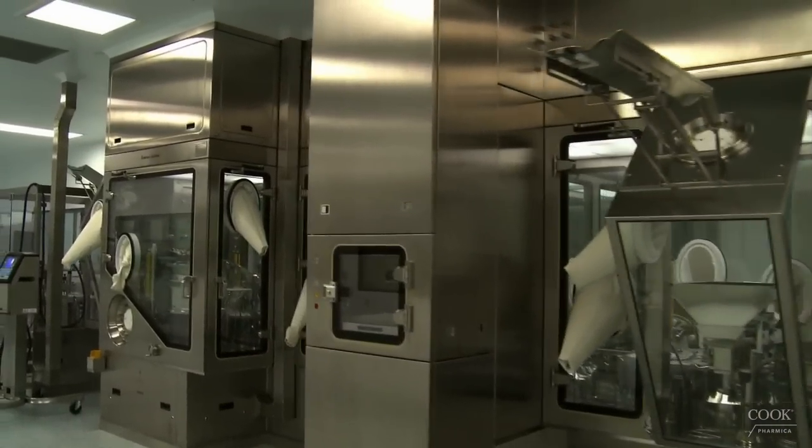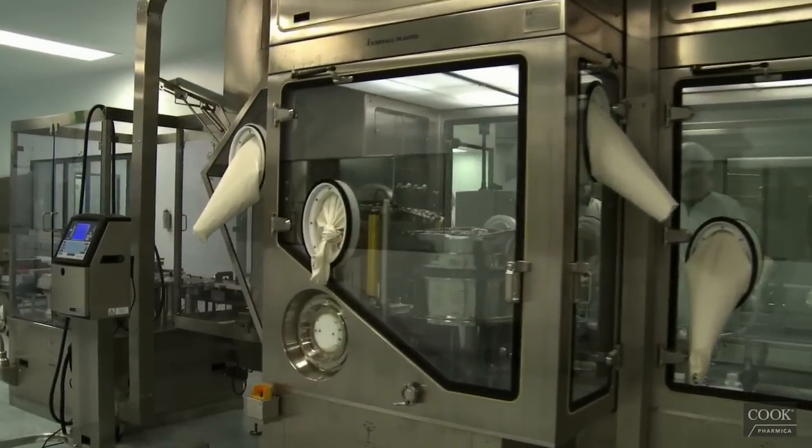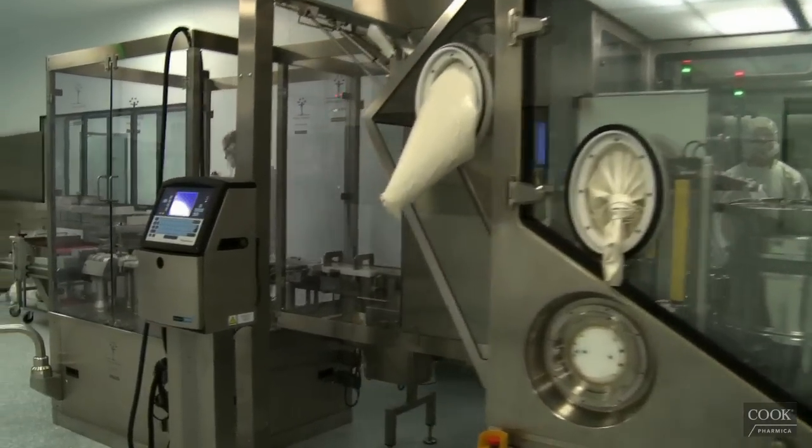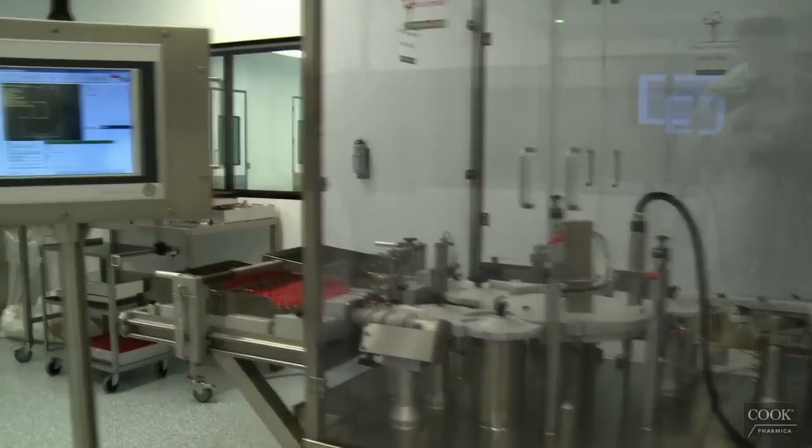Filling, row-by-row loading and unloading for lyophilization, and capping all take place under barrier isolation with the capability of filling 60 to 150 vials per minute depending on vial size and fill volume.